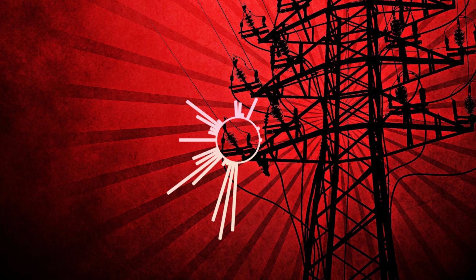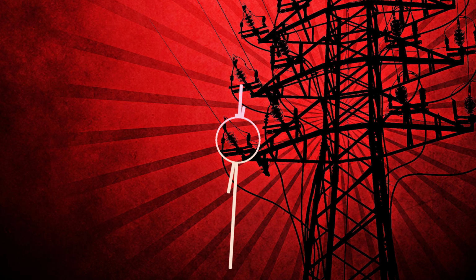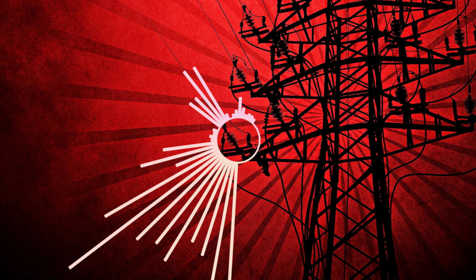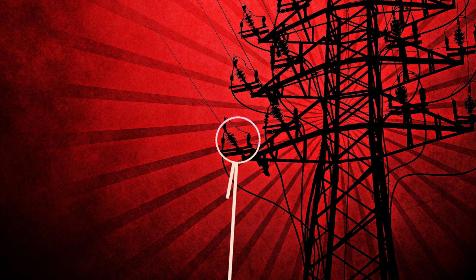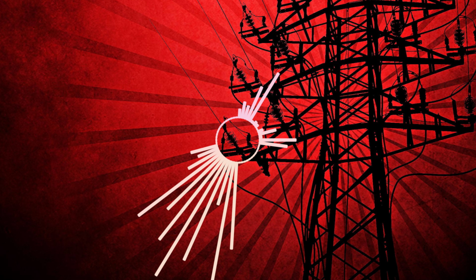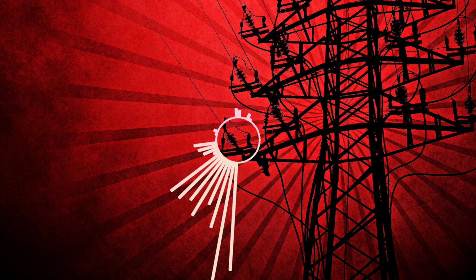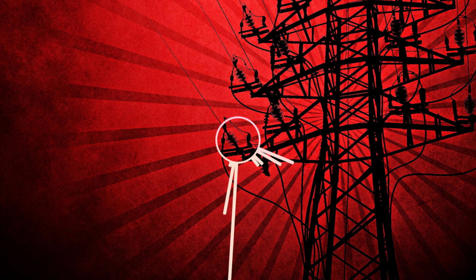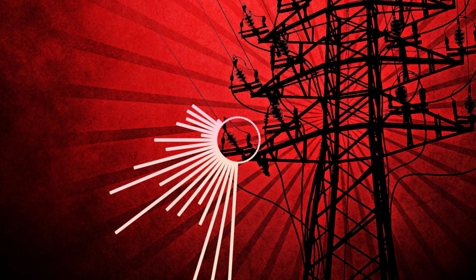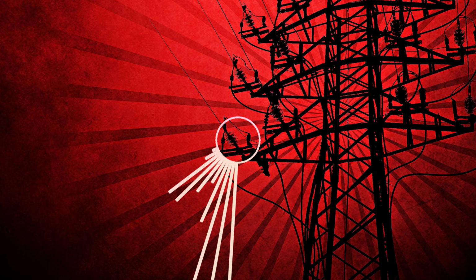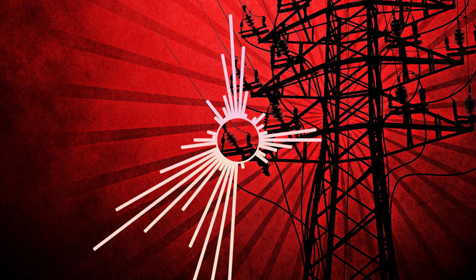If the electrical service equipment in these locations is rated for 1200 amps or more, it must have a permanent label applied to it. This label must provide some crucial information about the system's safety to help workers who may need to service or maintain the equipment.